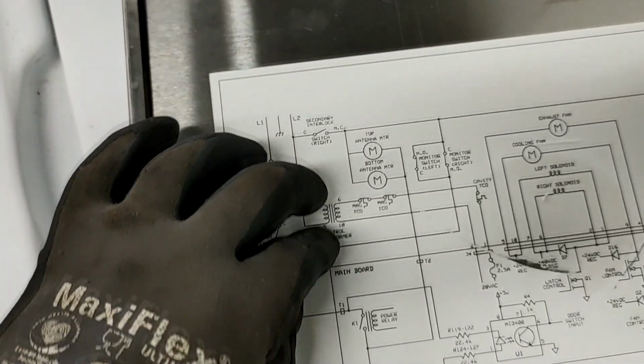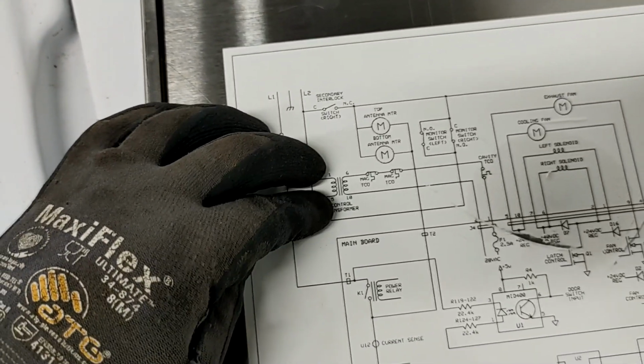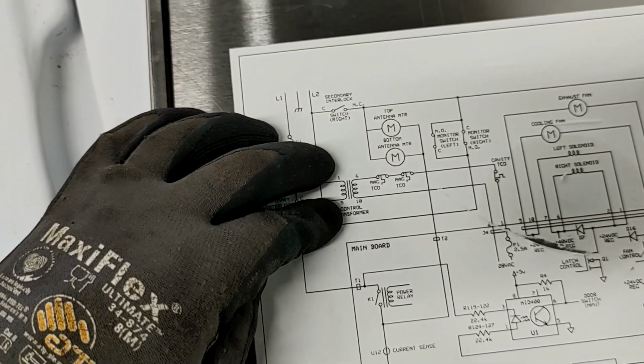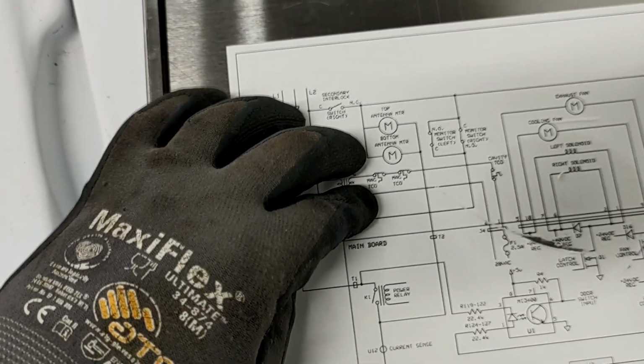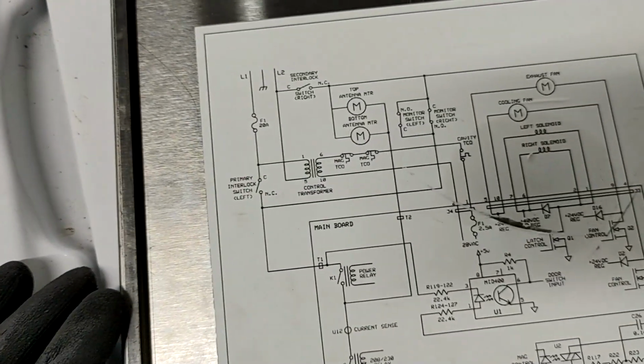Like I said, what you would do is check your input coming in - you should have 240 on pin 1 and 5. On the output, you should have 26 volts if that transformer is working correctly.